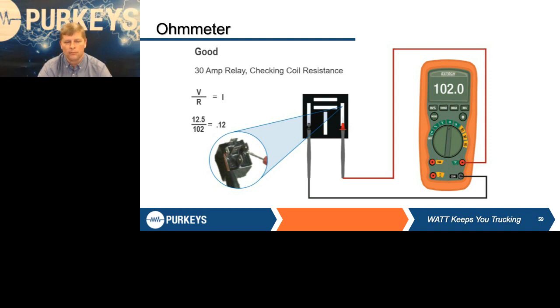Is that good or bad? The only way you know is you got to go to the manufacturer's spec sheet and says, hey, that particular model relay, it should be between 100 and 105 ohms. This one's right where it's supposed to be, so we know it's good. But what does that equate to? We're going to use the Ohm's law we talked about and take the voltage and divide it by the resistance. And that'll tell us what that coil should pull. So we take 12.5 volts, divide it by 102 ohms, says that relay coil should pull 0.12 amps, which is right where it should be.